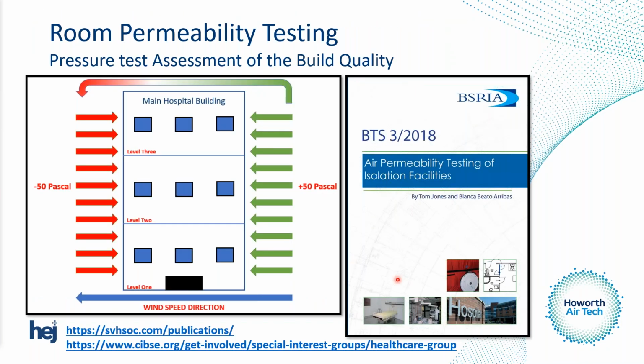So keeping permeability testing in our minds, obviously we do the mechanical ventilation system, we do the HVAC system, we do the ductwork arrangement in accordance with the relevant documents. And then we also have to assess the permeability test of the room. So this is a pressure test of the room, and we're basically checking the fabric and making sure that room is adequate for the purpose. So when we get to commissioning and validation, we don't want to be struggling to get our pressure regime. One of the questions we can answer at this stage is that the room pressure permeability test passed, so it can't be an issue with the actual fabric of the room. That's where we want to be.